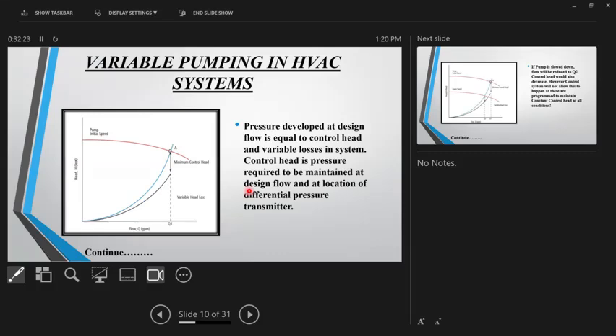One of the answers is variable pumping systems. Variable pumping systems can solve this problem to a very great extent. However, to apply variable pumping system logic correctly, we need to understand a few fundamentals. Again, I'll go back to my graph. The red line is the pump curve, let's say at full speed, and the blue line you can see is the system curve, correct? Wherever they meet, that's the operating point. Simple.